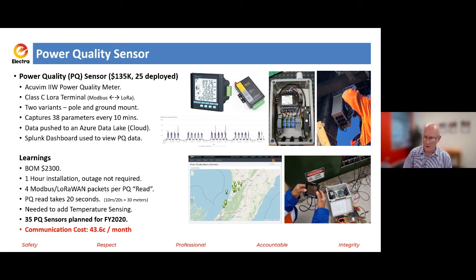We've got 25 meters installed, so we're right at the limit. We need to look at whether we slow the reading down or change our technology. One thing we identified was that we really should have added temperature sensing to the power quality sensor as well. We've got another 35 PQ meters planned for this year, so I need to work out the solution for that fairly soon. As a LoRaWAN device, it costs us 43 cents a month or thereabouts to communicate - quite economic.